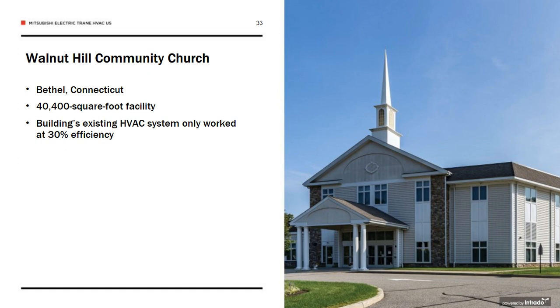Using linear expansion valve kits, their mechanical contractor proposed a solution to connect the existing air handlers with VRF outdoor units and controls. This provided the church with the energy-efficient advantages and precision control of VRF technology, without the huge task of removing and replacing the air handlers. With the upgrade, the church was projected to save roughly $50,000 per year in energy costs, leading to a payback of approximately 5 years on their investment.